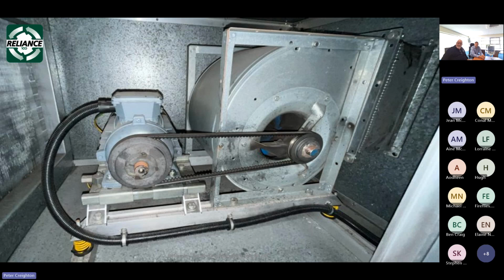Nowadays, people spend a bit more time, but still, how would I put this nicely? An air handling unit has a motor running, and it should not be running at 50 hertz, first of all. So it should be controlled by an inverter. The inverter should be controlled by a PID loop, which is watching your airflow, etc., and all coming back, and in doing so reducing the hertz.